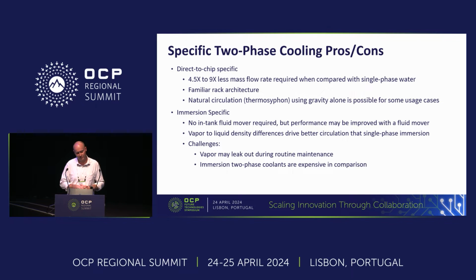There are even use cases, maybe not 100 kilowatt racks but more like 20 kilowatt racks, where it's possible with two-phase cooling mechanisms to passively circulate fluid, using the density difference to drive the fluid through, which could offer reliability benefits over a pump-based solution. For immersion cooling, with two-phase compared to single-phase, you probably don't need an in-tank fluid mover. It can be passive, and you get more fluid circulation in two-phase immersion than in single-phase immersion.